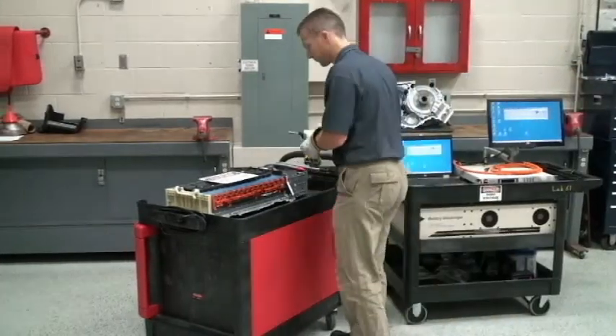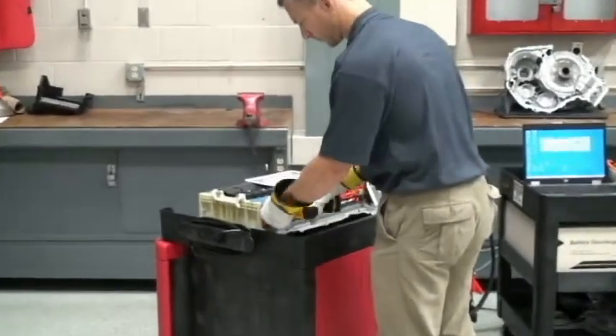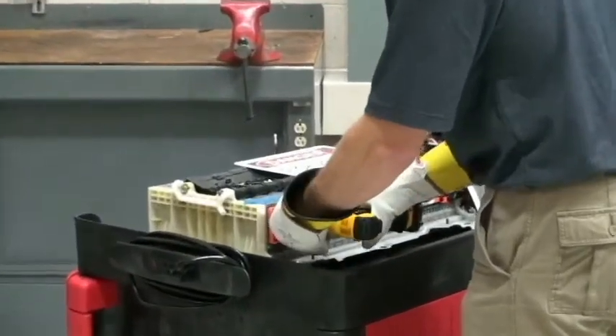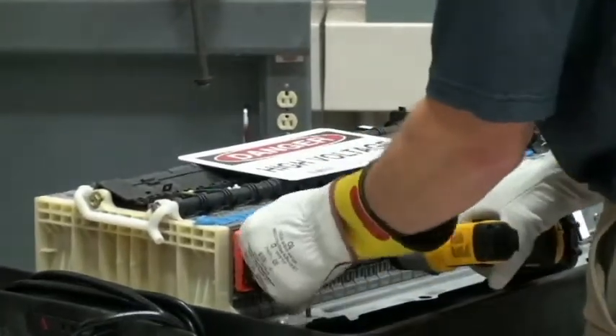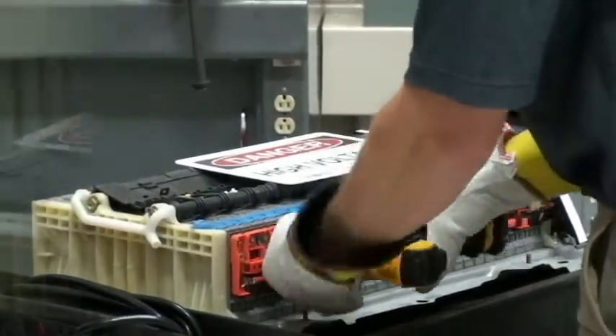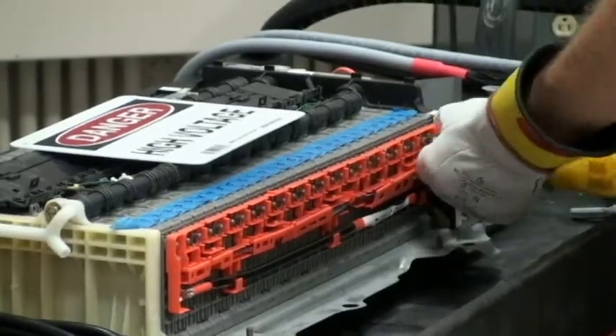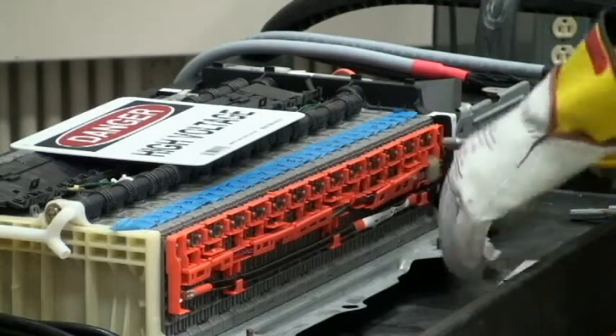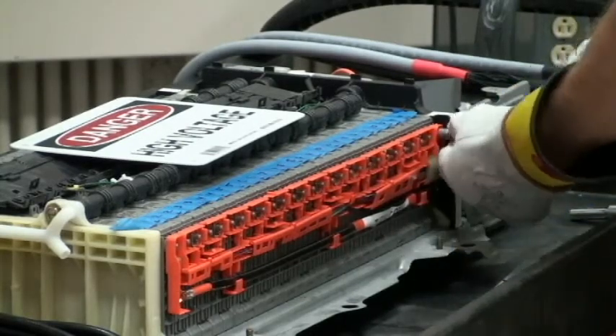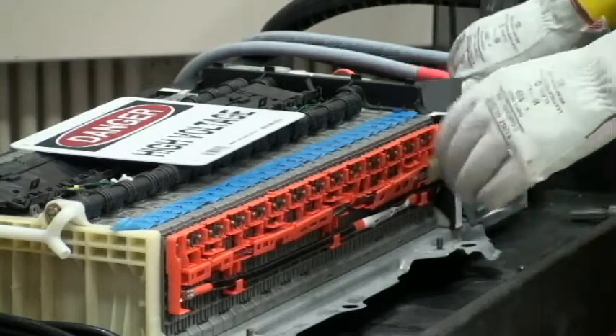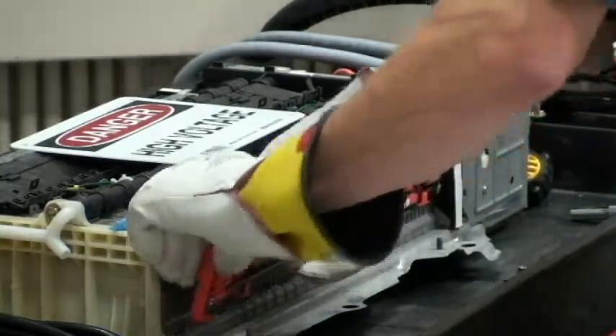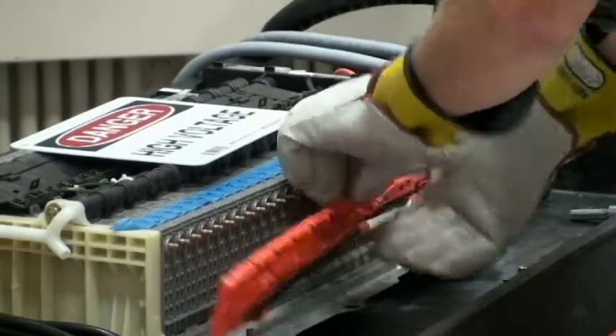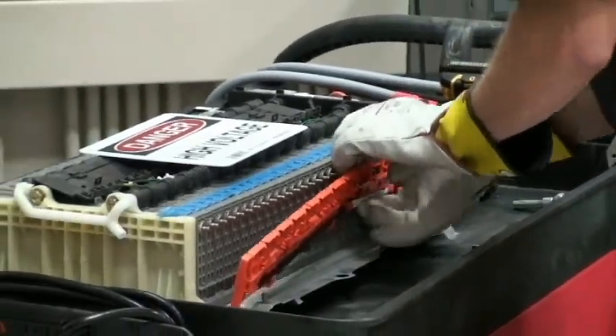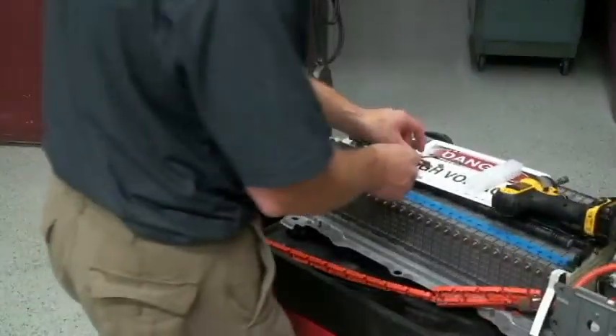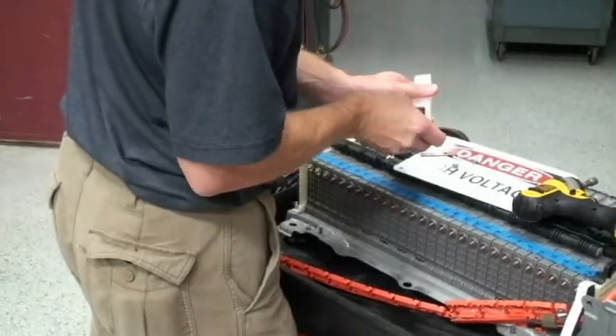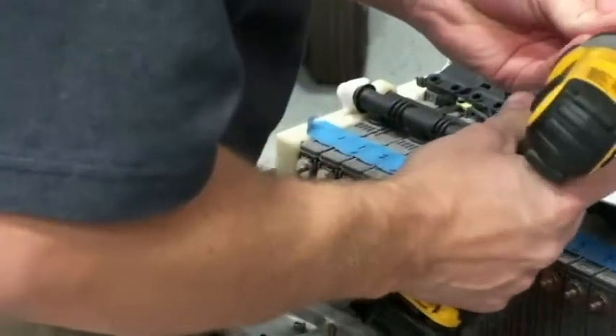The next step will be to remove one of the bus bars from the battery pack. Notice that the technician is wearing high voltage class 0 gloves when removing the nuts from the battery modules. Once all the nuts have been removed, the bus bar can be removed. Once a bus bar has been removed, the technician no longer needs to wear the class 0 gloves because the battery pack is now safe.